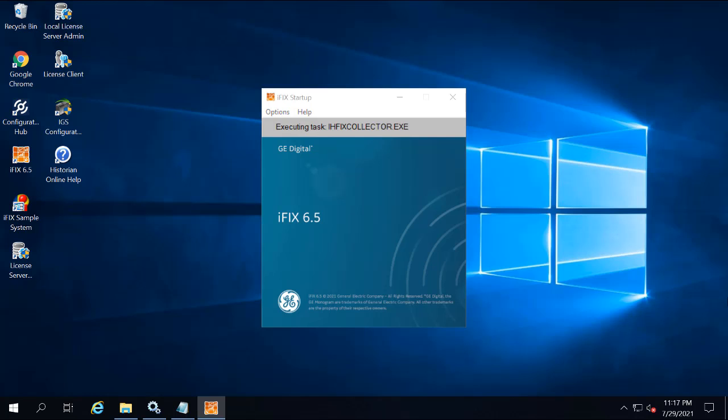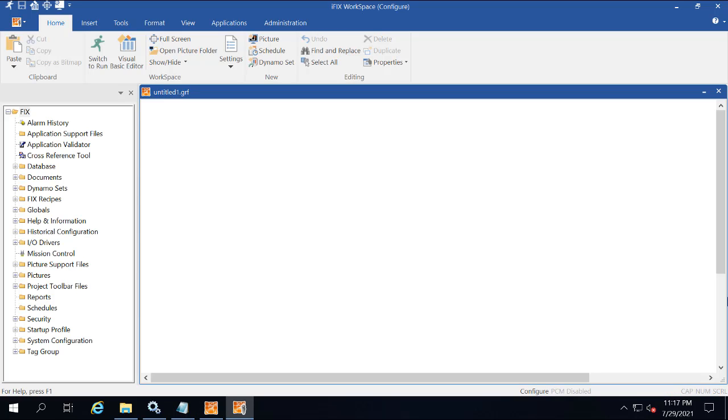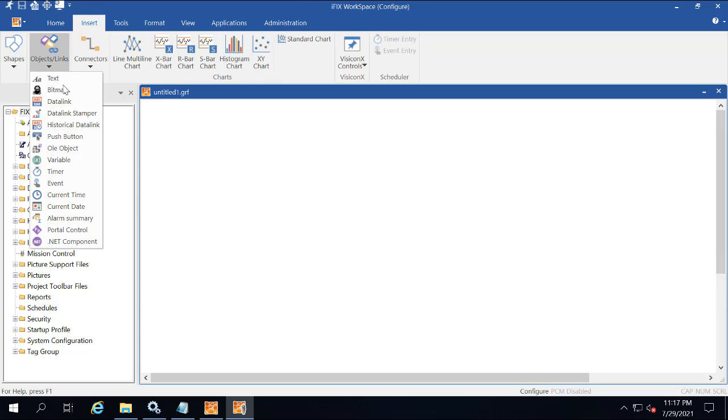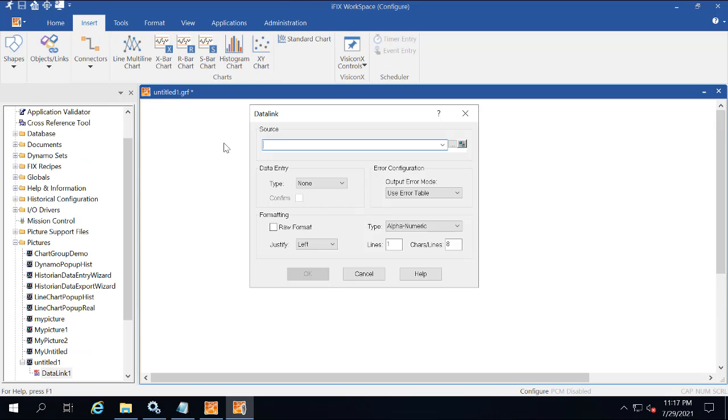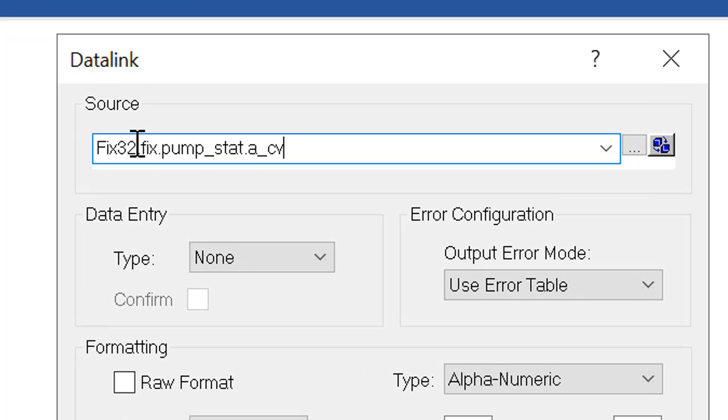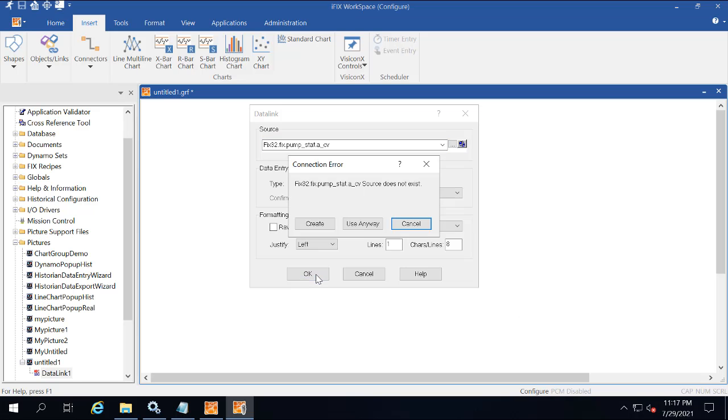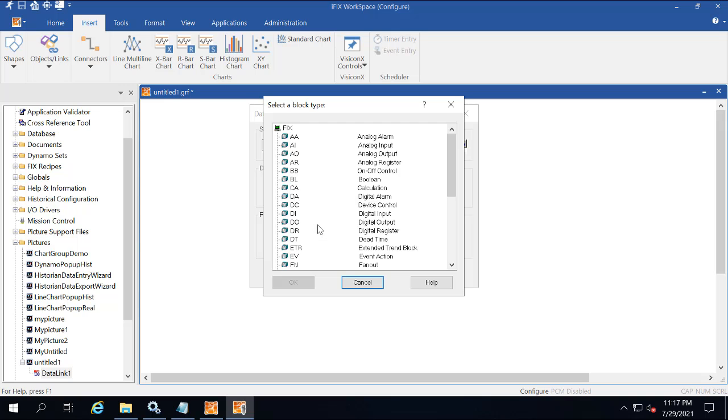In the iFix workspace, you're going to select Insert, Object/Links, and then the Data Link Stamper. Now in the data source field, you're going to enter fix32.fix.pump_stat.a_cv. You're going to be prompted to create a new tag, so click Create.